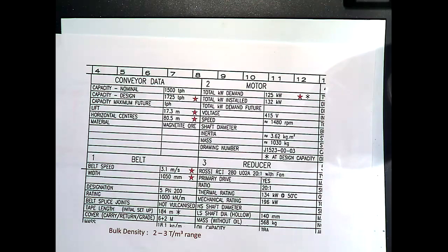Remember, if we go back and can I just click? Oh yeah, okay, I can go back. Look, remember that the conveyor that we're looking at is this one. Okay, so we're actually lifting. Now, if we're actually going down, we could actually generate some electricity, or we'd probably have to put in brakes and all this kind of stuff. And so, particularly belts that actually go up and down like this. Over some distance, they can be, you have to look at each bit because some you'll actually be putting power in, some you'll actually be getting power out.